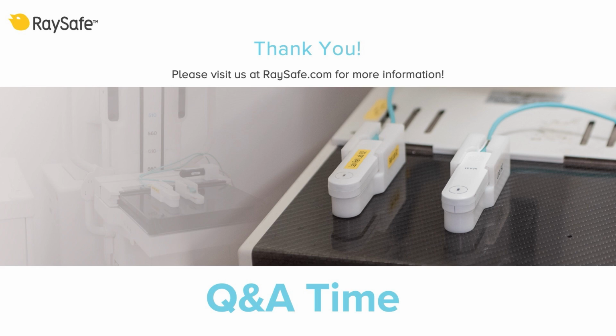Does the 452 perform dead time correction on the GM tube? Yes, the 452 performs dead time correction. So there's no need for the user to adjust the readings in any way.